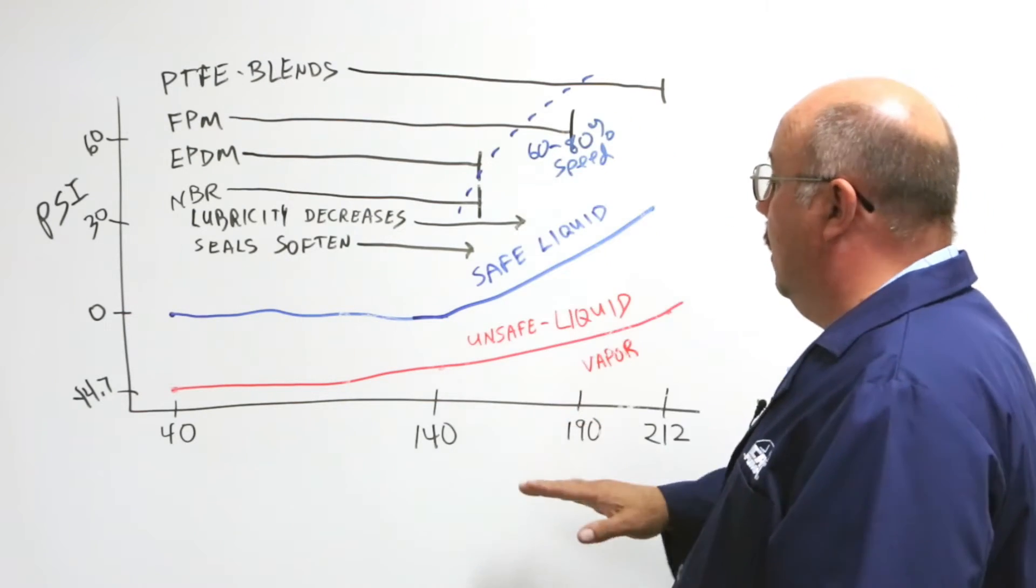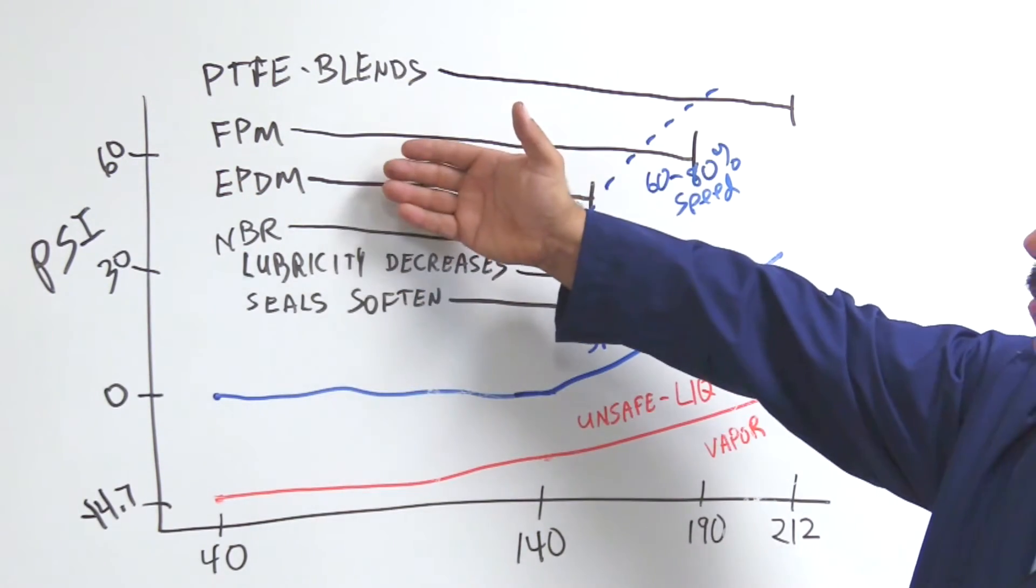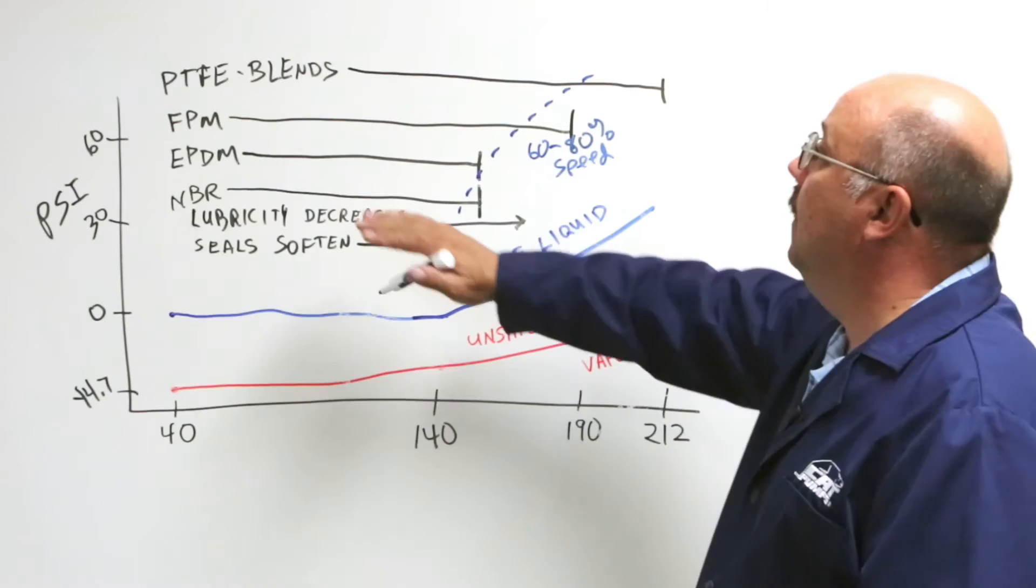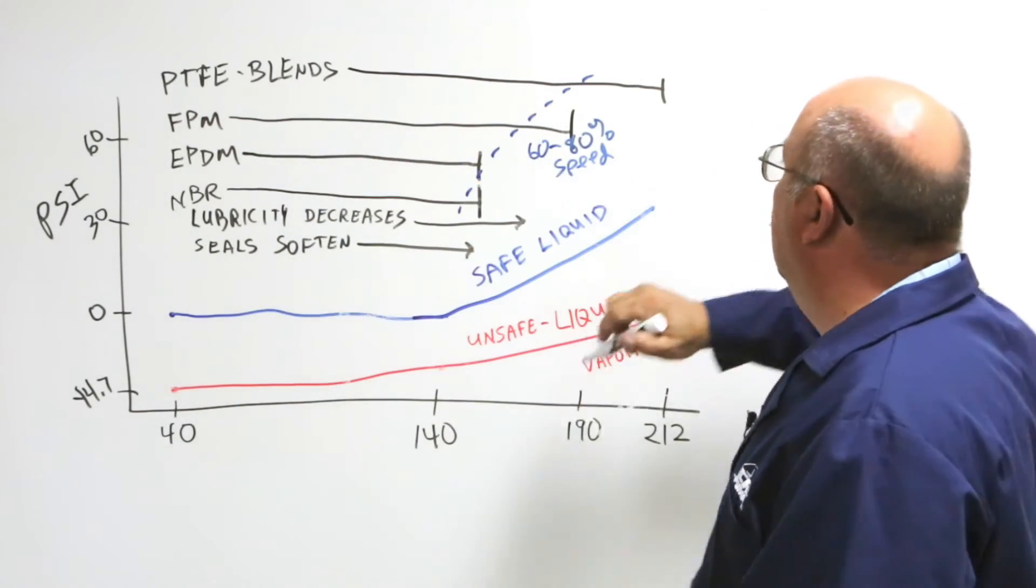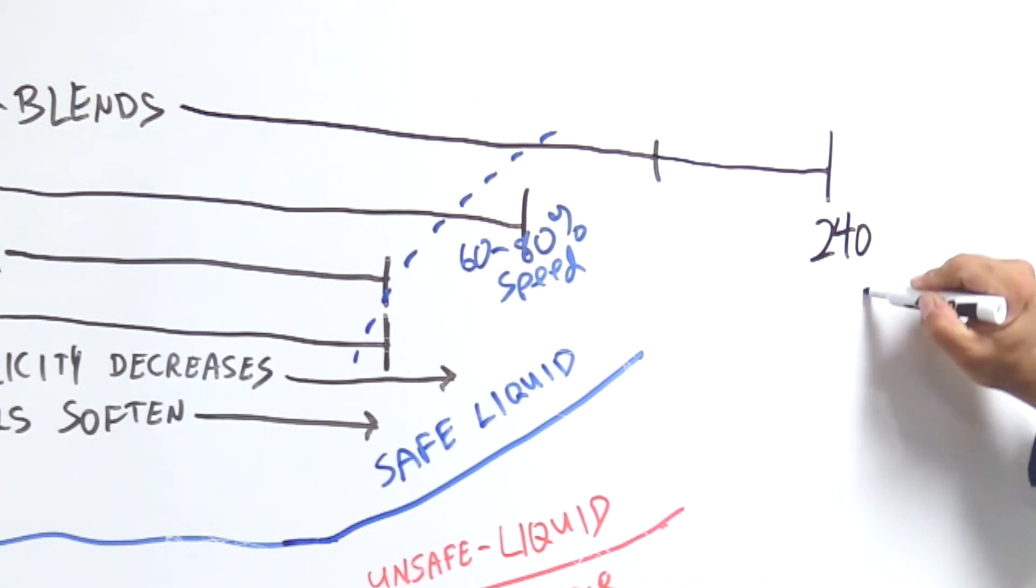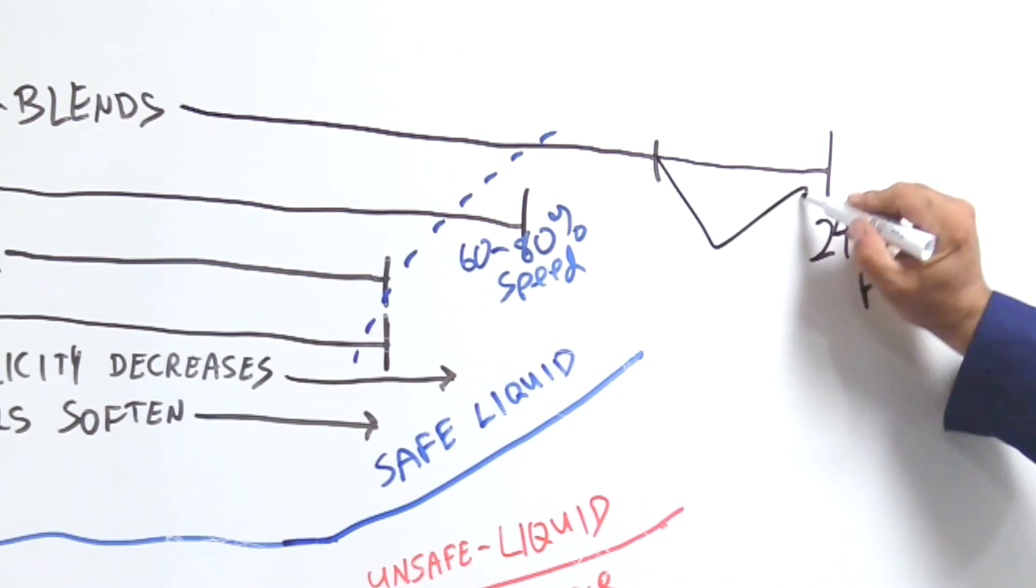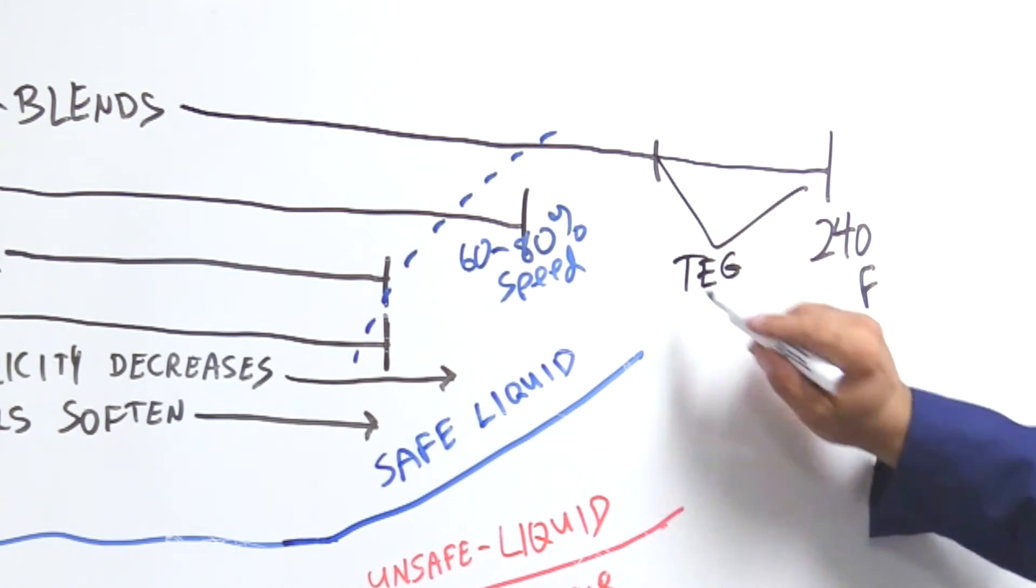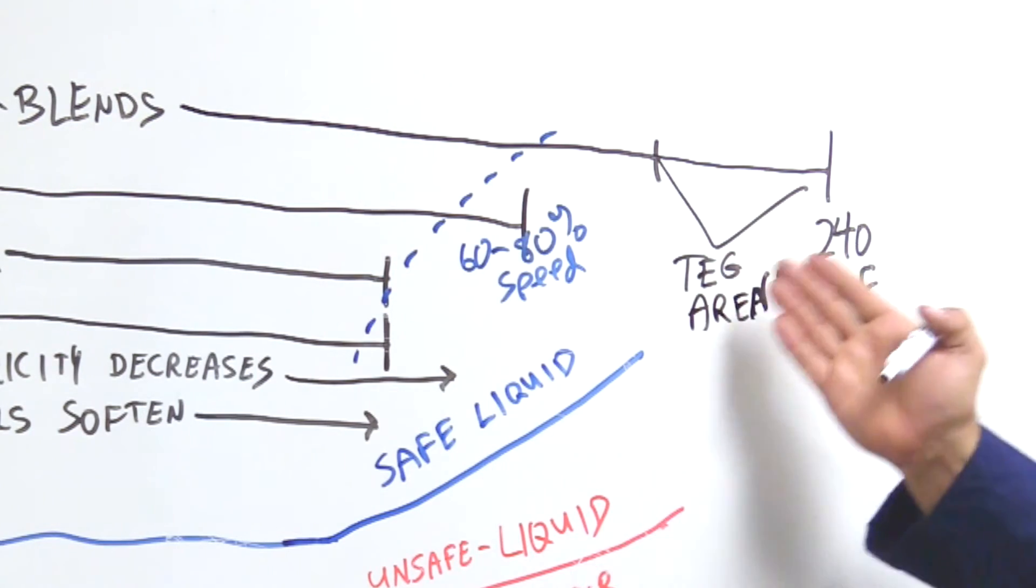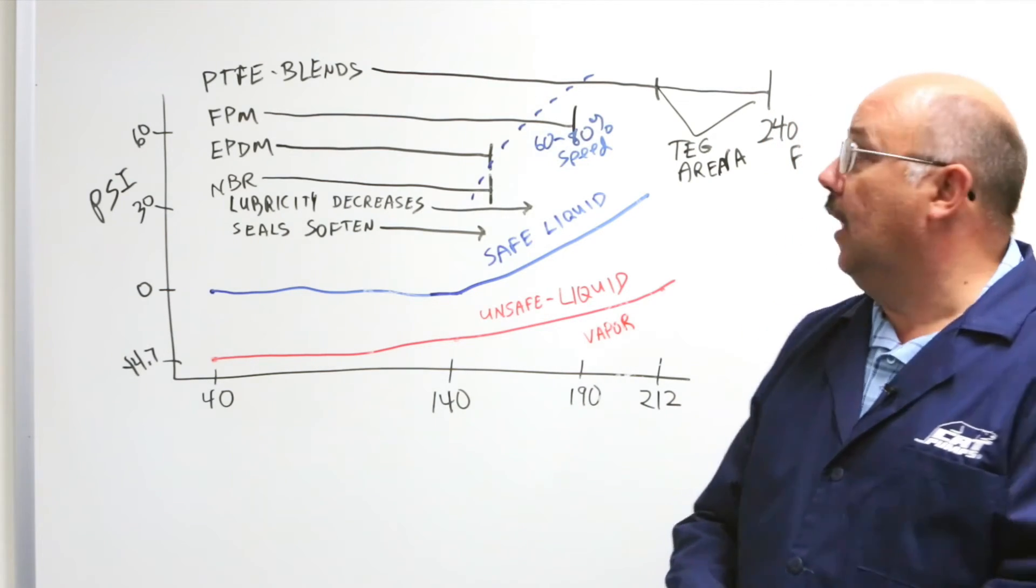So that's how we use temperature to dictate our inlet pressure and then these characteristics and the chemical compatibility to determine which seal materials we choose. Now the last thing I want to mention is the PTFE blends in specific. Remember I said they easily go to 212, well we can actually go up to 240 Fahrenheit if we are using a liquid that has really good lubrication properties such as TEG or triethylene glycol. In this arena of liquid we can pump that up to 240 because at these elevated temperatures it still has good lubricity properties to give us long seal life with the PTFE blends.